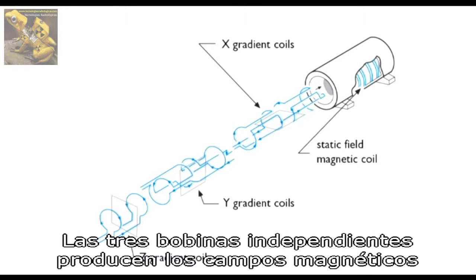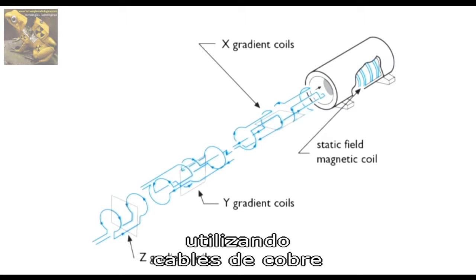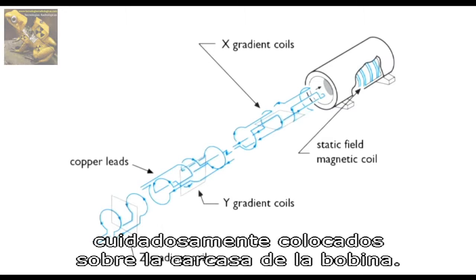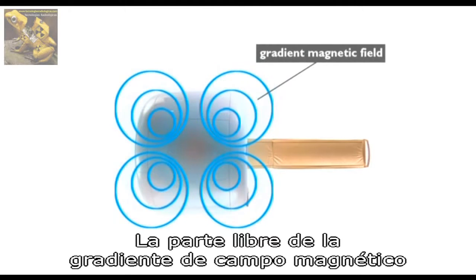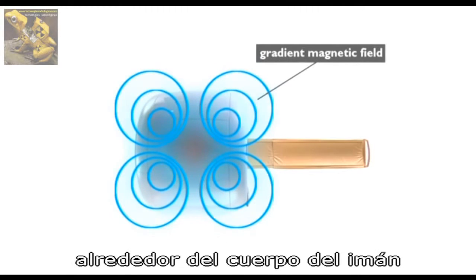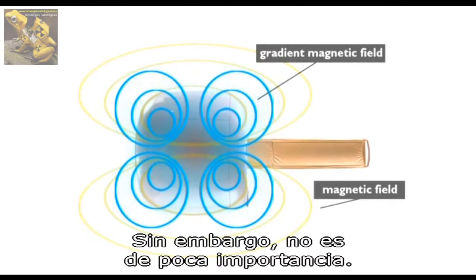The three independent gradient coils generate the gradient magnetic fields for each of the three orthogonal directions and are created by copper leads carefully positioned on the coil housing. The stray field of the gradient magnetic field outside the magnet bore is much smaller than that of the main magnet, but may not be neglected.